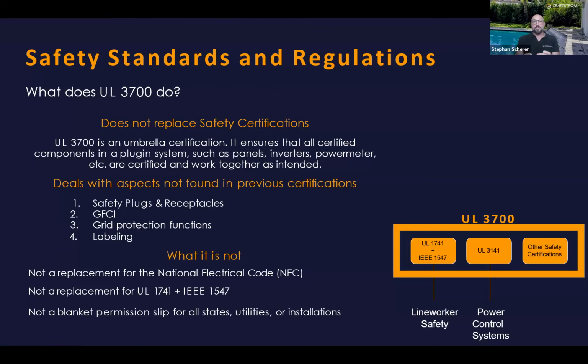But before we get to UL 3700, every manufacturer has to go through various other safety certifications that are not being replaced by this. So I mentioned UL 1741. That's in combination with IEEE 1547, mentioned here on the second from bottom line. That's probably the most important one that everyone discusses because we always hear, but what about line worker safety? This is the standard that tests how quickly an inverter can shut off in case of an outage. It's one of many certifications, but this is the most important one.